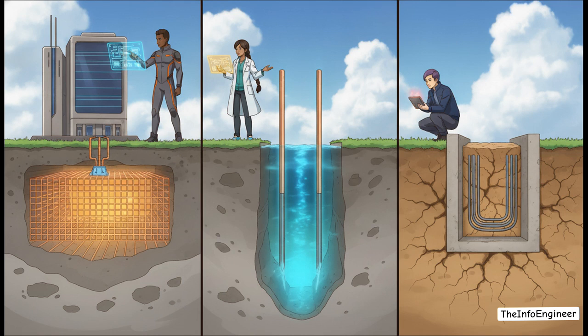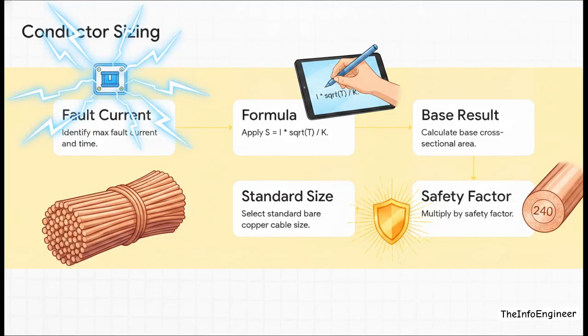This is a brilliant, concrete-encased method invented during World War II for bomb storage vaults. It uses the naturally high pH and moisture retention of concrete to give you an incredibly low-resistance path to ground, even when the dirt around it is completely dry. And please never just guess your wire size.